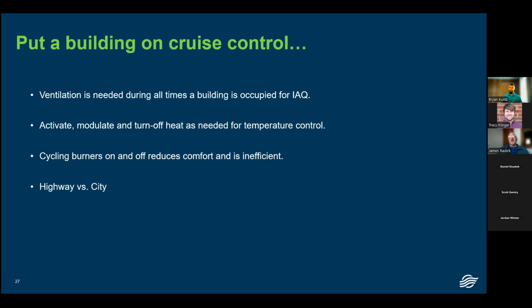That's why this is a unique concept. It's been around a long time, but people just don't understand it. So we actually have our air controls designed so that they will adjust. If somebody sets it to 60 degrees for a desired space temperature, it'll automatically cap the maximum temperature going out 30 degrees above that. That way people can't inadvertently cause themselves harm in building performance.